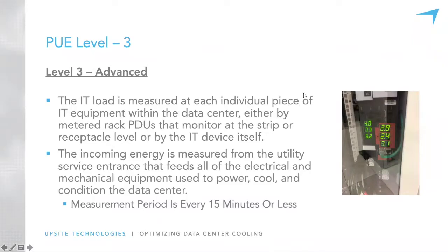Finally, PUE level 3, this is what we would consider, or the Green Grid would consider, advanced. I see a lot of DCIM solutions now that have PUE modules in them where it's measuring the PUE real time as you go. When we look at PUE level 3, the IT load is measured back to the power distribution units or the power strips within the rack. I've taken a picture of what one in a newer rack in our data center looks like, and also through our DCIM solution, we are able to see what our load is there. And again, the PUE level 3 is basically real time where it is constantly measuring that load, and it allows you minute by minute to see where you are.